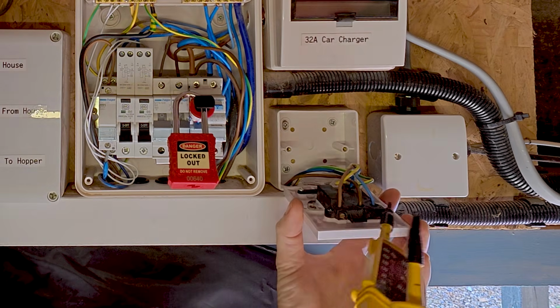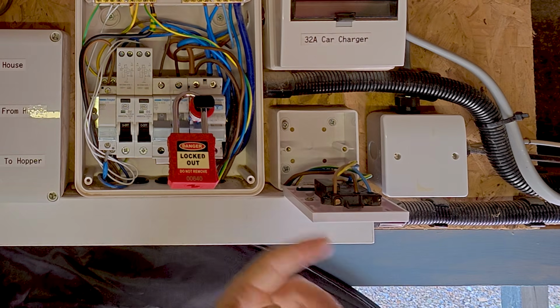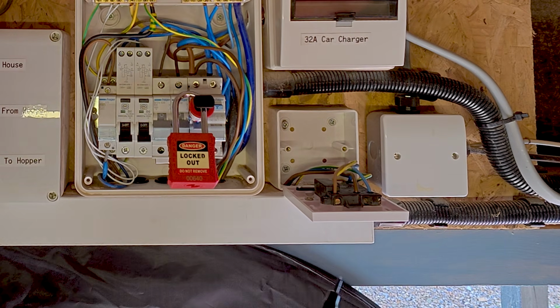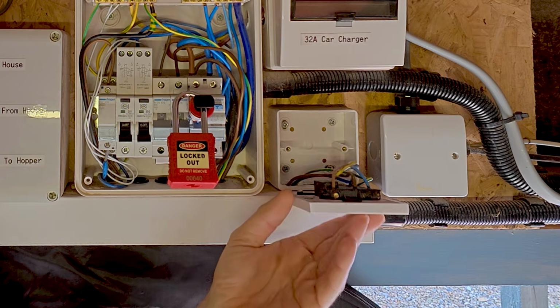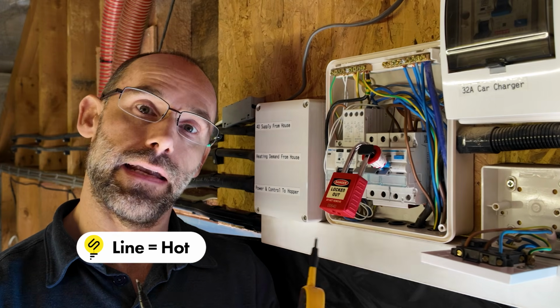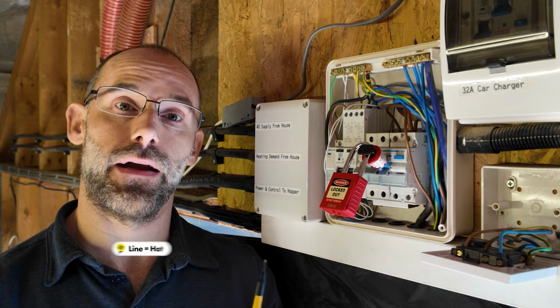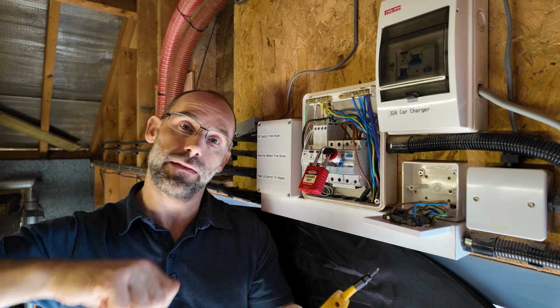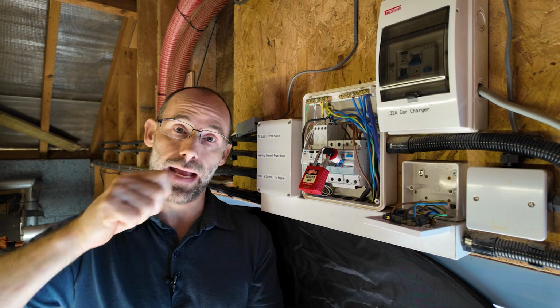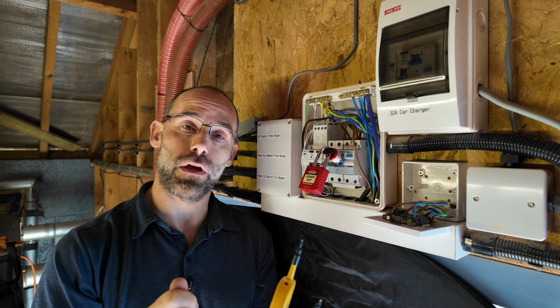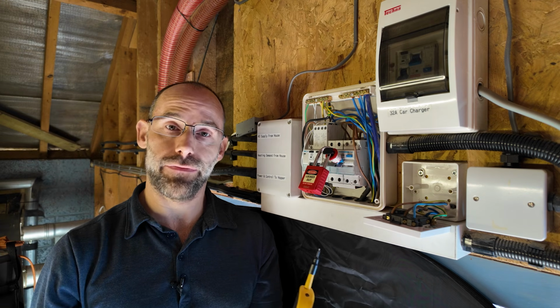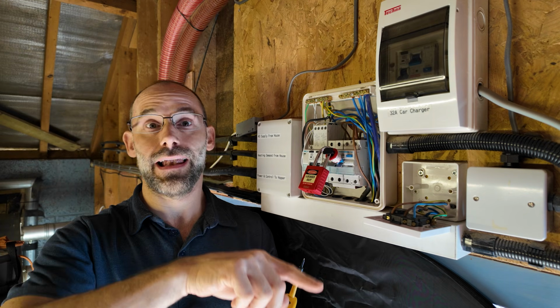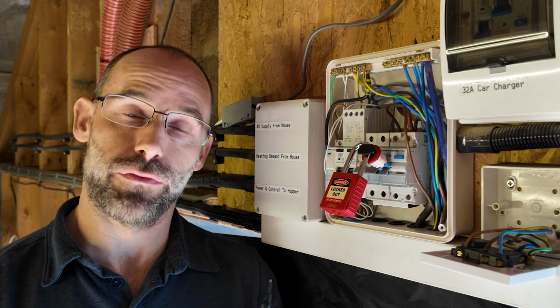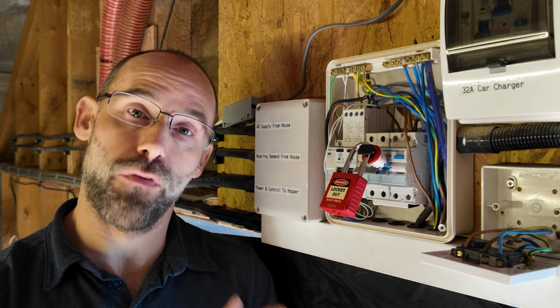thing. Now, you may think you've plugged it into the right terminals on here, incoming and outgoing in the right place, but it is important that when we turn something off, that we break the circuit on the line side, not the neutral side. If we break a circuit on the neutral side, it's after the load, right? So the power goes out to the boiler, and then you break the circuit on the way back. Yes, it'll stop the thing functioning, but the problem is you've still got a line conductor going to this big metal boiler. Not safe. We need to break the line conductor before the load.